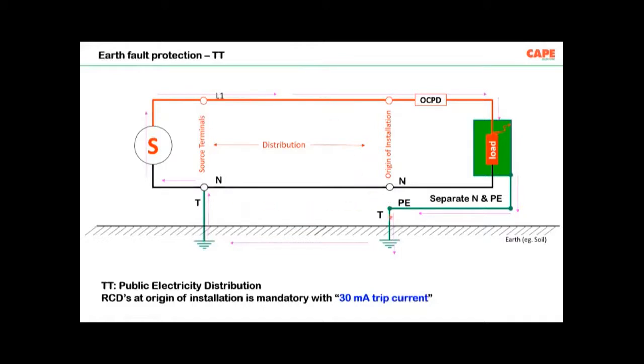Now, under this condition, the resistances of the earth electrode at the source side and at the equipment side will come into the picture. As a result, the fault current will be very much less. The fault current is not enough to trip an MCB. As a result, the very simple solution provided in the standard is that you put a 30 milliampere RCD at the origin of the installation. I have shown the RCD as a series device, but I'm sure every electrical engineer will understand. This is just to show you there is a protective device. So in a TT network, for fault protection, a 30 milliampere RCD is mandatory as per this particular standard.